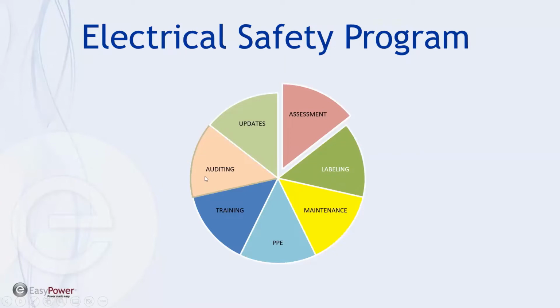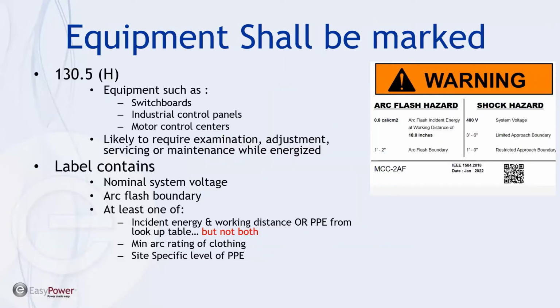The arc flash assessment is not the first and last step in an electrical safety program. It's actually the beginning of an entire cycle that needs to include labeling, maintenance, PPE selection and use, training of personnel, auditing the system as we use it, and then incorporating updates both in our organization and our facility, as well as the standards being used. NFPA 70E Article 130.5 requires that equipment such as switchboards, industrial control panels, and motor control centers that are likely to require examination, adjustment, or servicing while energized require field labeling. And the label shall contain nominal system voltage, arc flash boundary, and at least one of incident energy and working distance or the PPE from lookup table, but not both.